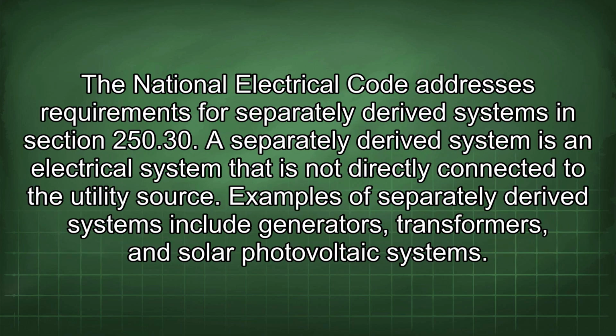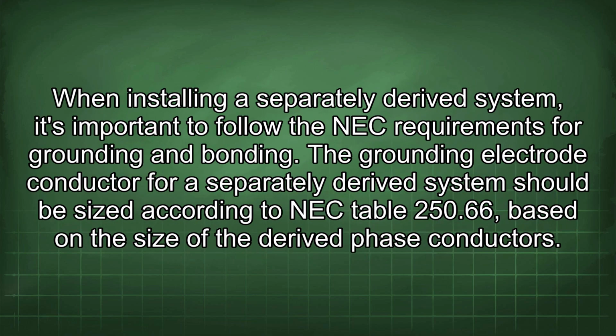The National Electrical Code addresses requirements for separately derived systems in Section 250.30. A separately derived system is an electrical system that is not directly connected to the utility source. Examples of separately derived systems include generators, transformers, and solar photovoltaic systems. When installing a separately derived system, it's important to follow the NEC requirements for grounding and bonding.